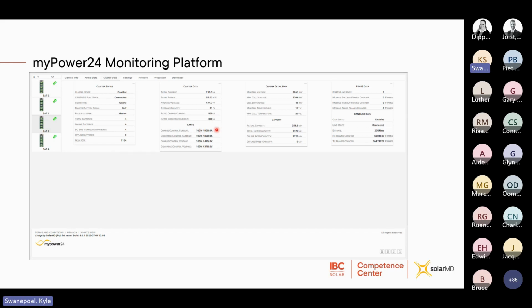And it's 800 amps limit because each battery is rated at 200 amps. The discharge is exactly the same because we're in normal operation. So we also have a discharge limit of 800 amps. And then the charging voltage, this will change based on the number of modules you have connected in series. So the bigger the HV battery, the higher this voltage limit will be. The current will always be 200 amps per battery. And then the same goes for the discharge voltage. This is the current discharge voltage limit, and this will also increase based on the size of the battery.